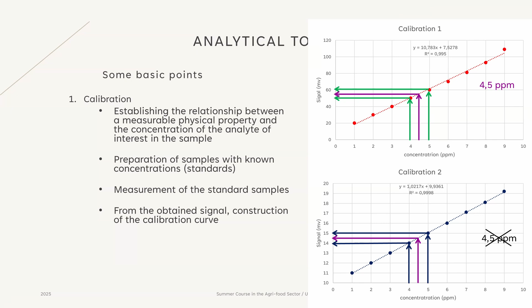So we have to pay attention to the coefficient of regression, for sure. We have to produce a very high regression coefficient. However, it is even more important for us to get very high slopes in our calibration curve. As you can realize here, using the same system, I can determine 4.5 ppm or not. I can even determine 4.1 or 4. Here, I can go directly from 4 to 5. So this calibration curve is much better than this one because the slope is larger. I'm going to come back to this in a few minutes, but I think I demonstrated that the slope is quite important for calibration.